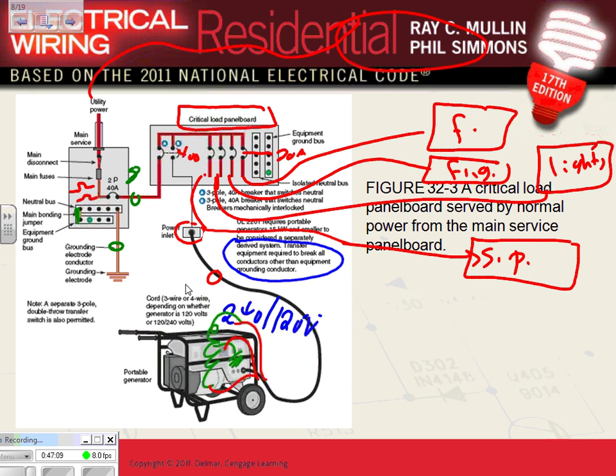So you have to switch the neutral through these 3-pole circuit breakers that switch the 2 hots and the neutral, and they're bonded right in here, the neutral, so you don't have to bond again. Chris, if you can look here, I'm not bonding in the panel because it's bonded right through the transformer. We'll talk more, guys, about separately derived system, but it is when you bond the neutral and the ground at the generator here. If you don't bond them, it becomes non-separately derived system. Any question about this?